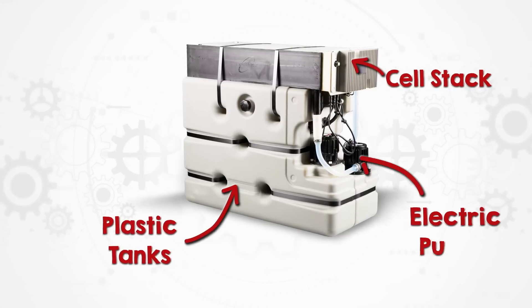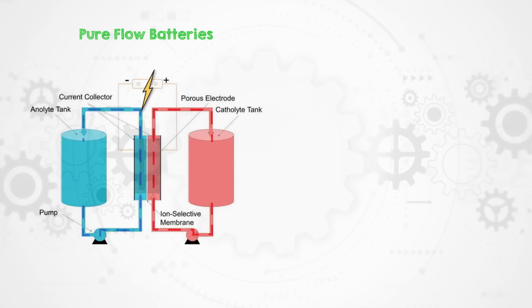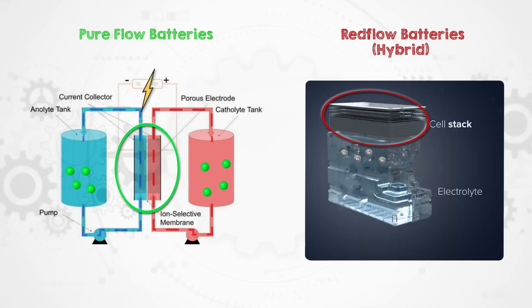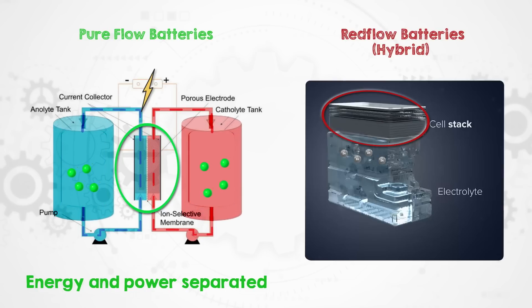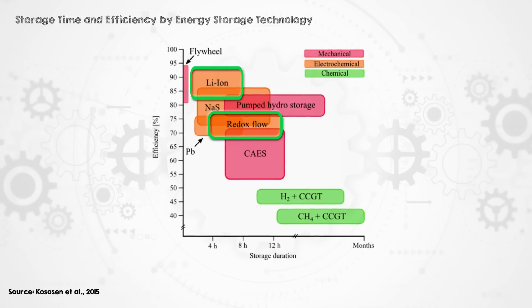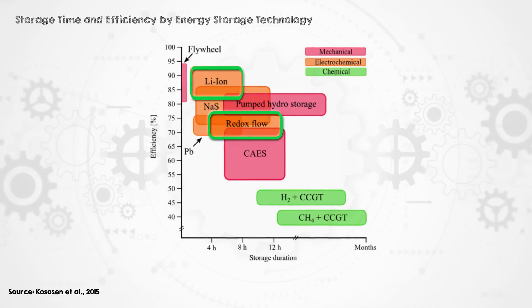In addition to that, there are just plastic tanks to hold the electrolyte and electric pumps to move it through the cell stack. Some of you may be familiar with flow batteries and might be thinking this Redflow battery is a bit unusual — and you're right, it's a hybrid flow battery, not a pure flow battery. In a pure flow battery, the reactions take place in the electrolyte at the electrodes and the ions remain in suspension. Whereas the Redflow battery stores energy by physically plating zinc out of the electrolyte onto the anode, then releases energy when the zinc is returned to the electrolyte. This means a pure flow battery's energy and power can be completely separated — longer storage simply comes from larger tanks. In a Redflow battery, longer storage requires more anode surface area, but the total space taken up is about half that of other flow battery chemistries. Efficiency is similar at around 70–80%, comparable to pumped hydro or compressed air.